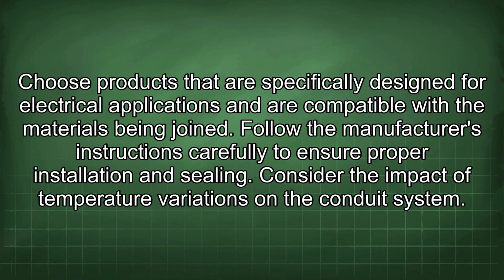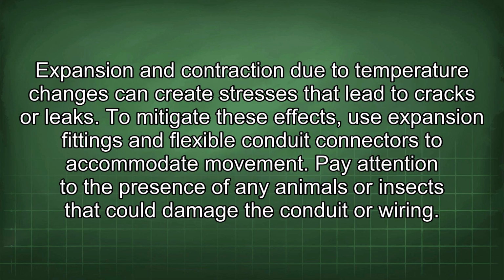Choose products that are specifically designed for electrical applications and are compatible with the materials being joined. Follow the manufacturer's instructions carefully to ensure proper installation and sealing. Consider the impact of temperature variations on the conduit system. Expansion and contraction due to temperature changes can create stresses that lead to cracks or leaks. To mitigate these effects, use expansion fittings and flexible conduit connectors to accommodate movement.